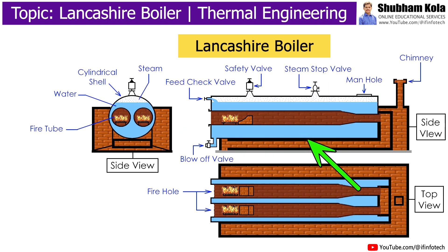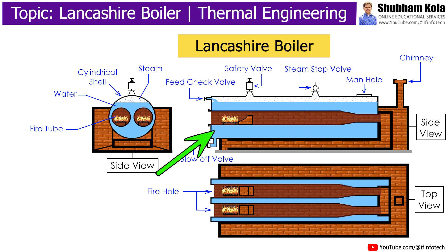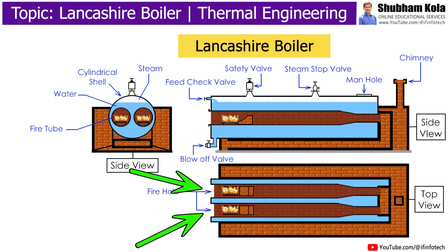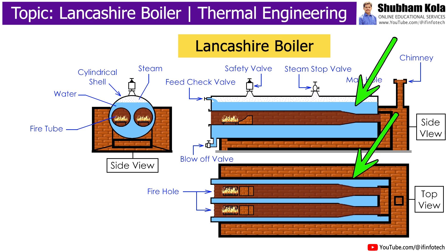The cylindrical shell is placed over brickwork which creates several channels for the flow of hot flue gases. The fuel is provided through a fire door and burned on a grate at the front end of each fire tube. The fire tubes are slightly conical at the rear end to increase the velocity of hot flue gases.